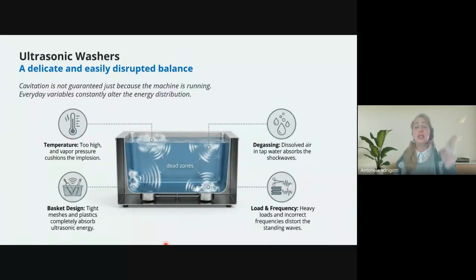Okay, so just turning on the machine and hearing the sound of transducers working and seeing some waves on top of the solution does not mean that everything is working correctly and that the cavitation energy is what is necessary to clean my instruments. Okay, so we have to make sure that every day, every time we change the solution, we have a new system. Okay, so what was maybe working in the previous cycle could not work this time. Many things can happen. And even more if we change the solution to a new one.